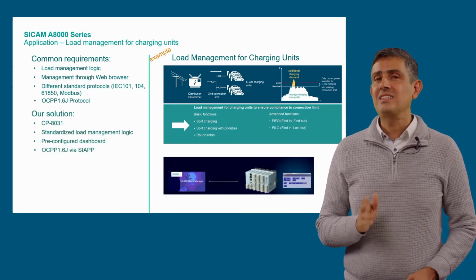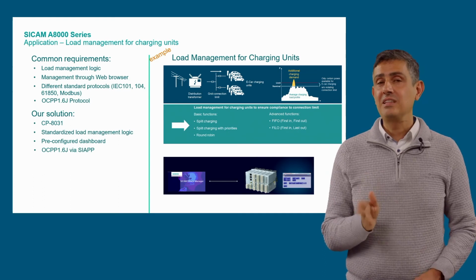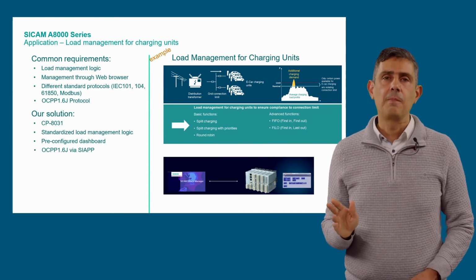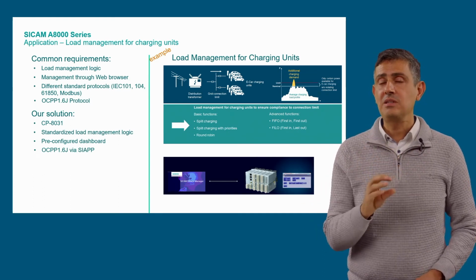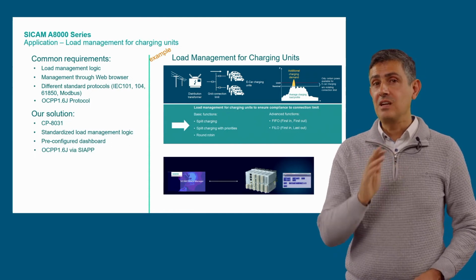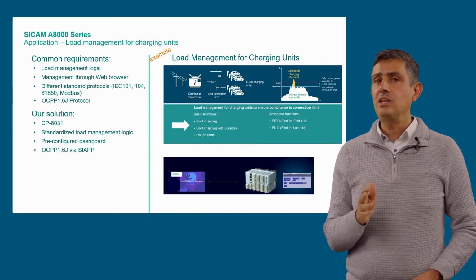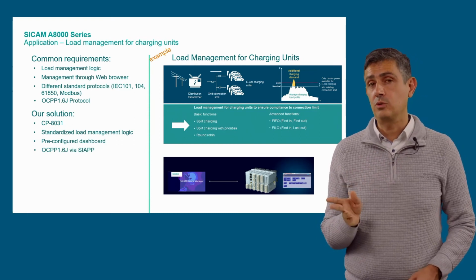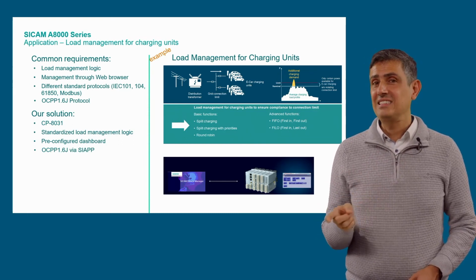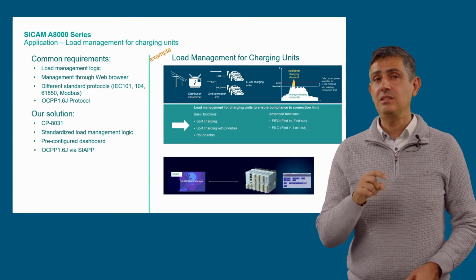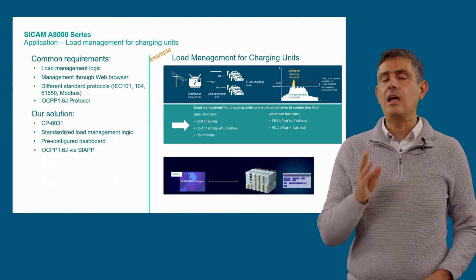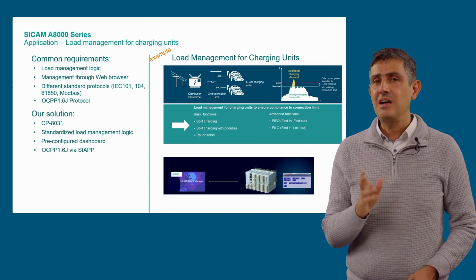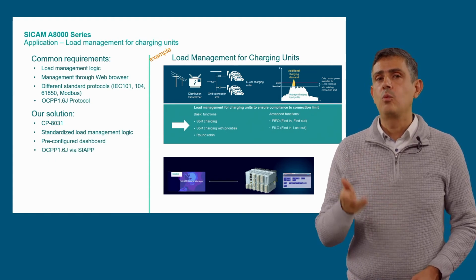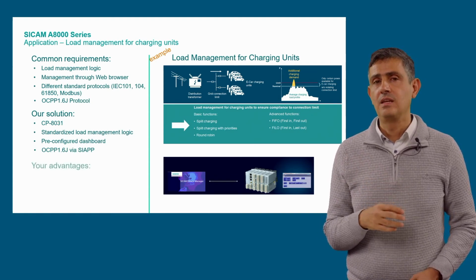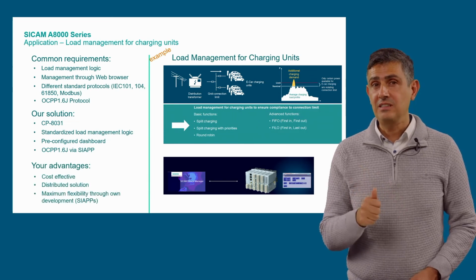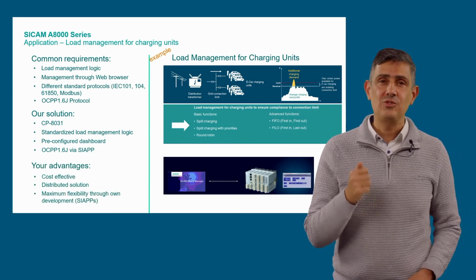Our solution would include a CP8031, which fulfills by default almost all these requirements. The load management logic has been implemented through CFC Logics, supports a friendly web-based interface, and can communicate through almost all the required communication protocols. The only one not supported by default by the CP8030 or 31 is OCPP. However, a SIAPP has been prepared to perform this task within the SICAM A8000. With this solution, you get a cost-effective and efficient solution to fulfill these requirements.